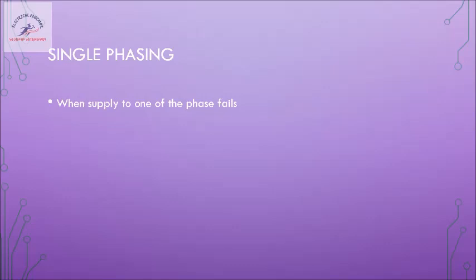Because as per Kirchhoff's current law, the current entering the node should be equal to the current leaving the node. So even though there are two phases connected, at a given point of time, current will enter the motor windings from one phase and leave from the other phase. So that is why we call this concept single phasing. We don't call it two phasing.